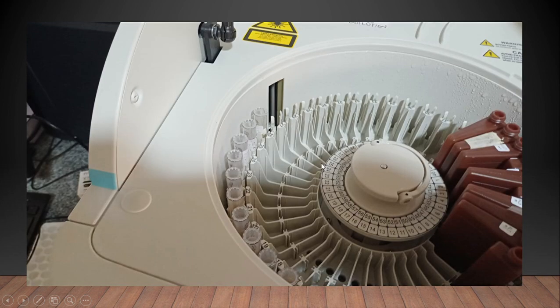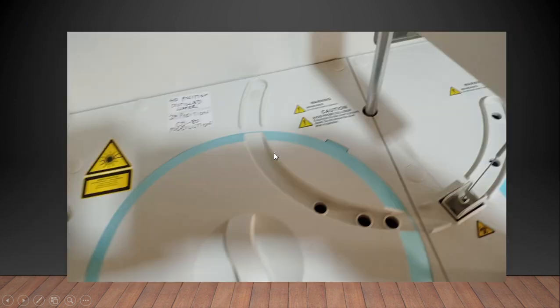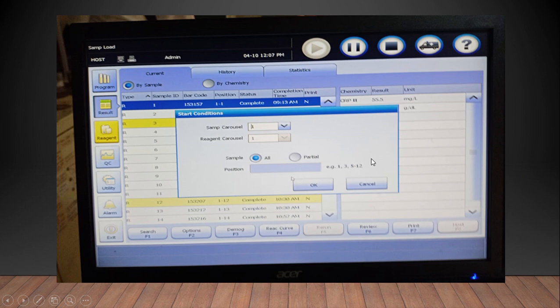Okay, so once the cap is removed, you put the samples in the positions mentioned in that list, that is 23, 24, 25, 26. So you have put it, and then you have replaced the cap. When you are replacing it, please note that the positions are proper, like this is the area where the cap has to be properly placed, and your half circle should be properly completed. Once that is done, you go to the play button.